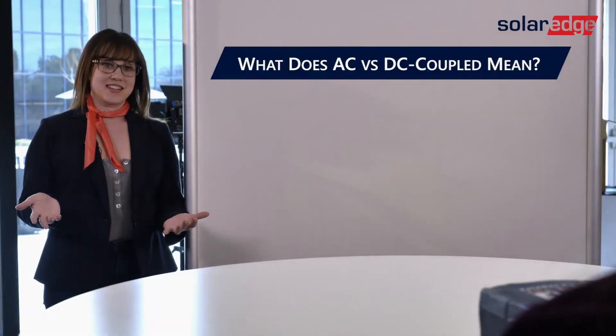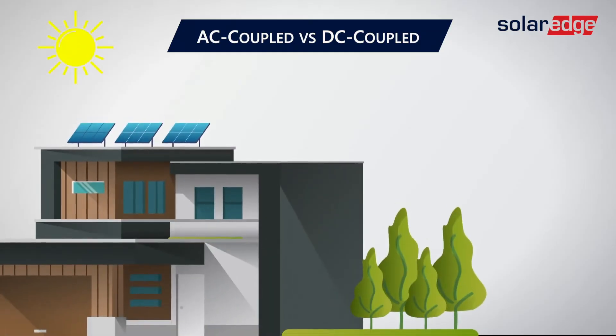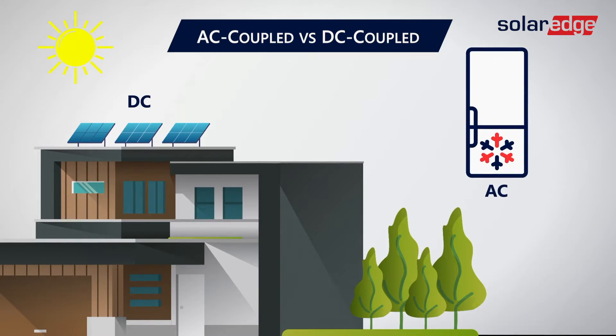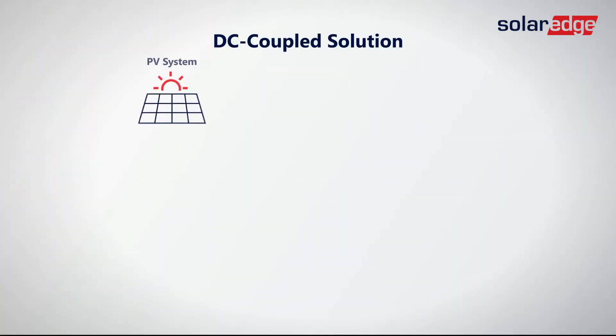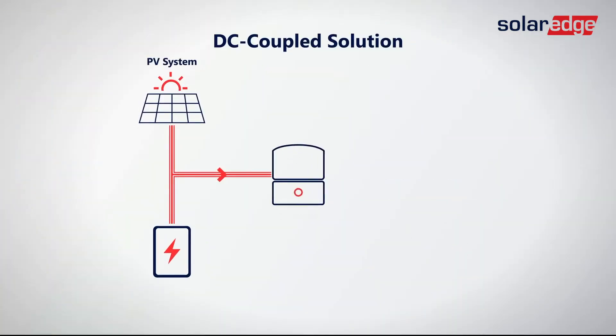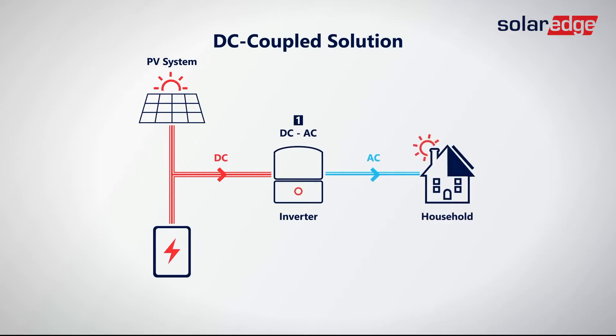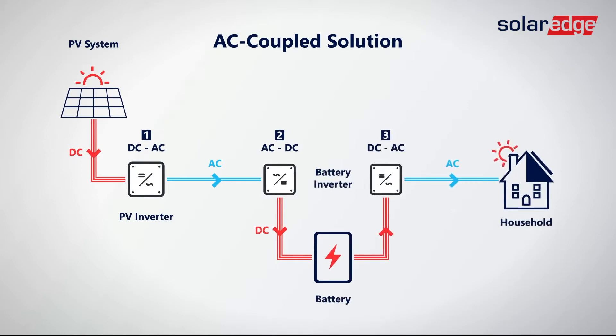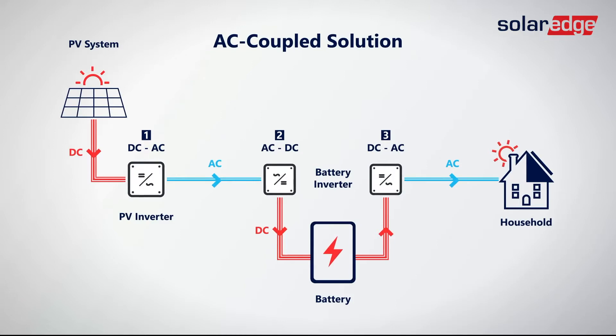So let's start from the beginning. What does AC versus DC coupled even mean? We know that the energy coming from our solar panels is DC, or direct current. But the energy we use to power our appliances requires AC, or alternating current. For that reason, we need to convert that energy for home use. In a DC coupled solution, the solar modules and batteries sit behind the inverter, both on the DC side of the system. But in an AC coupled solution, the modules and batteries work independently from one another, with the solar modules on the DC side and the battery sitting on the AC side of the system.